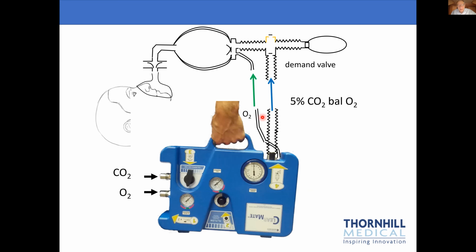So we designed this where we start off with the oxygen is plentiful, and you only need 5% of what you breathe in to be carbon dioxide, so we can have a small cylinder of carbon dioxide and provide the treatment whenever you have oxygen, which you would have anyway if you were treating the patient just with oxygen. And this provides the 5% CO2 and balance oxygen.